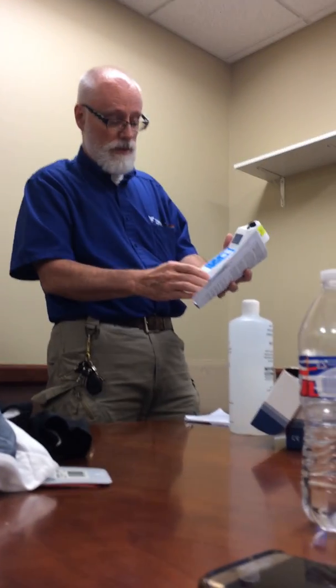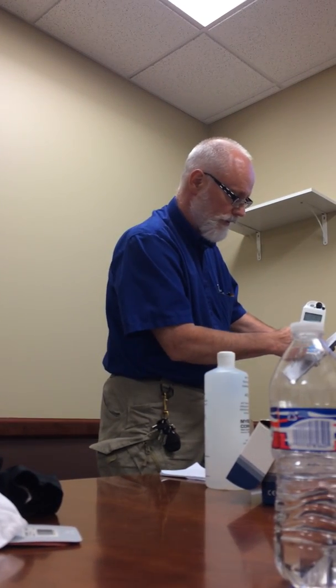Because these people are new, they don't know how to calibrate. So just show them how to do it anyhow, even if it is in range. So all you're going to do is, whatever number you got there for TDS, and you want to calibrate it, you're going to hit this 1 time, cal. And then whichever direction you got to go, you go up or down. And then just look and make sure it's right on 3000. Then you hit cal again. When you hit cal again, sometimes the number will change just a little bit. But if it's within range, then you're fine. You have a huge range actually. It's not huge, that's only 1%. Then you're going to dump that solution out.